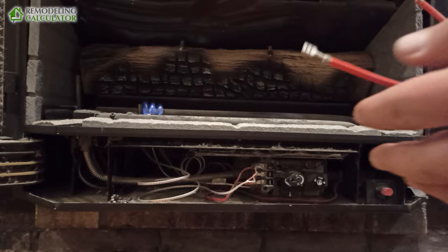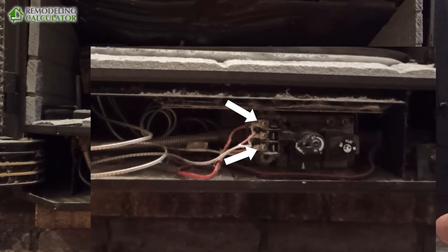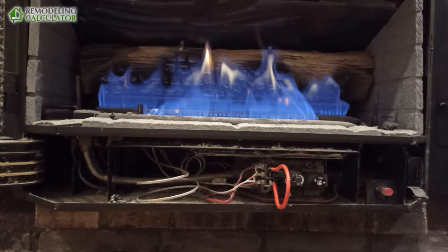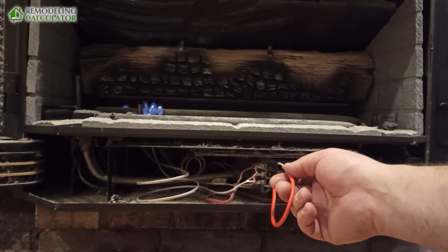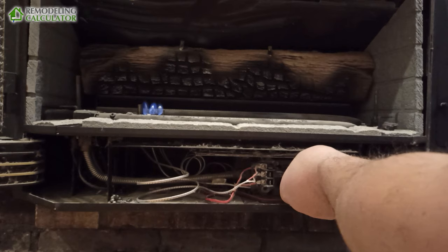The way we test it is with a jumper wire. You see this red wire — it goes to the switch. One end comes here and one is here. The switch breaks the circuit and the high limit also breaks the circuit. So if we jump this directly — there you go. This tells us the thermocouple is good, the thermopile is good, and we have a problem with our switch or our high limit.